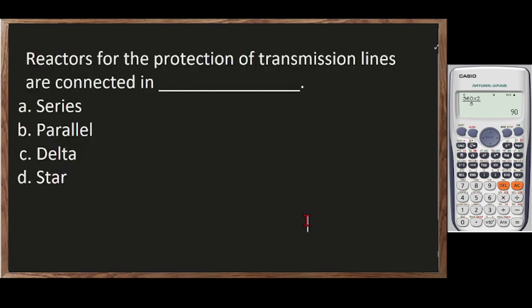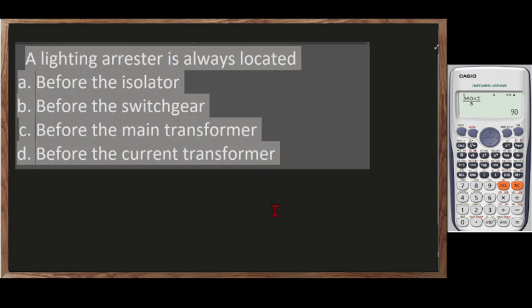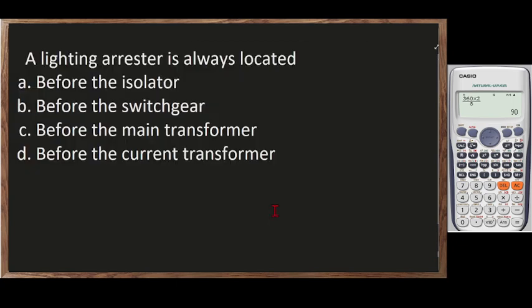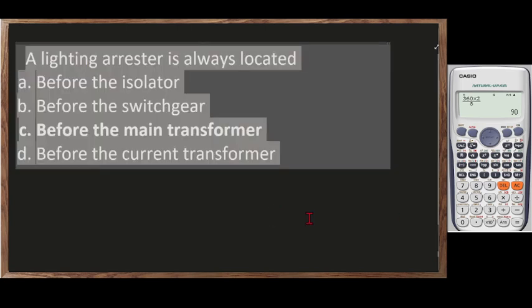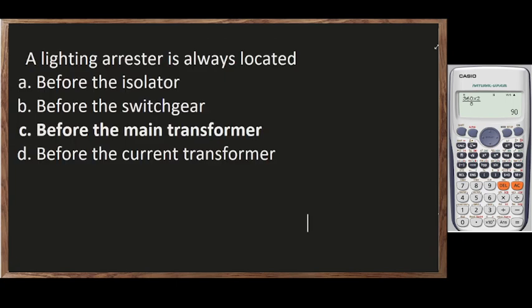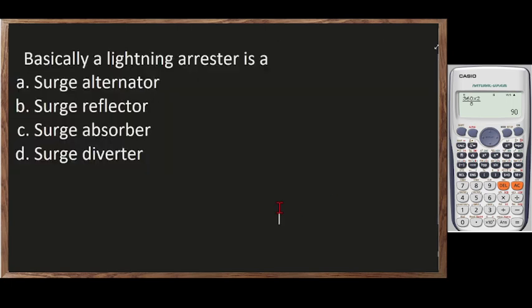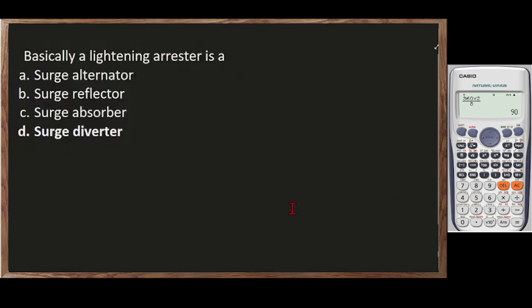Okay. Reactors for the protection of transmission lines are connected in blank. So yung reactors, so it is connected in series, parallel, delta, or star. Correct answer is letter A. So it is connected in series. A lightning arrester is always located before the isolator, before the switch gear, before the main transformer, or before the current transformer. Okay, the correct answer is letter C, before the transformer. Next. Basically, a lightning arrester is a surge attenuator, surge reflector, surge absorber, or a surge diverter. Okay, the correct answer is letter D, surge diverter.